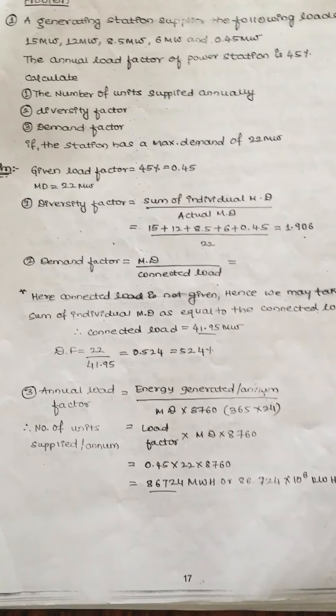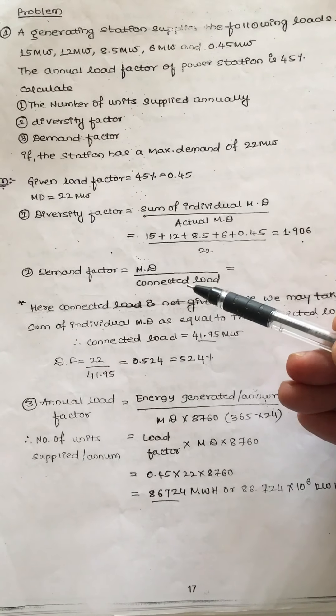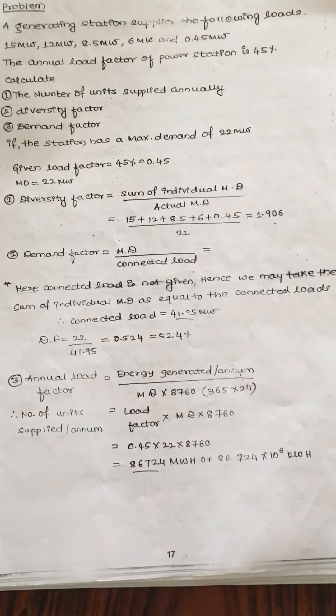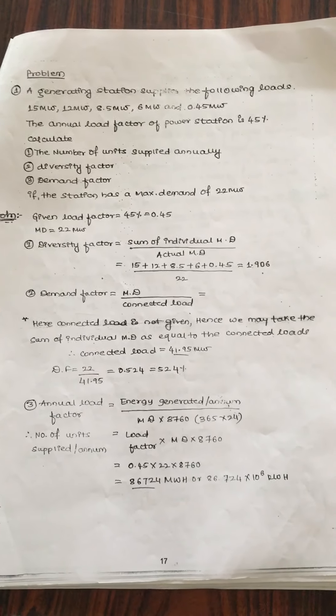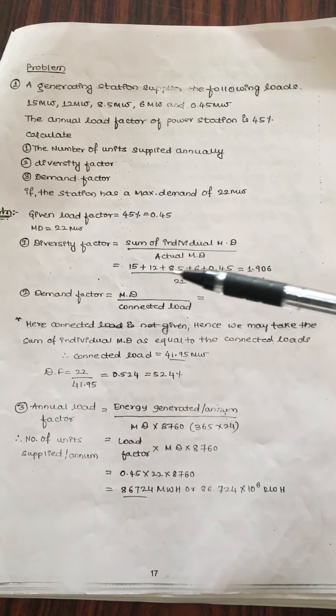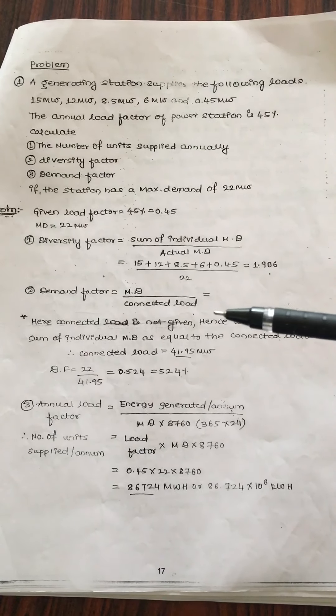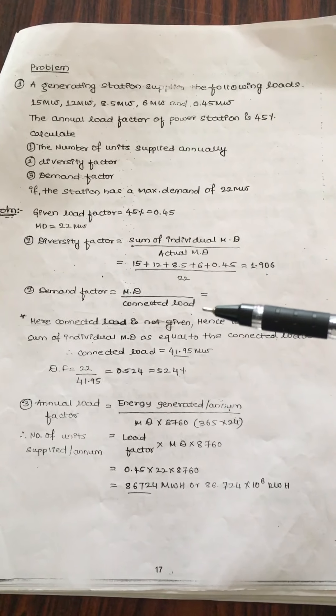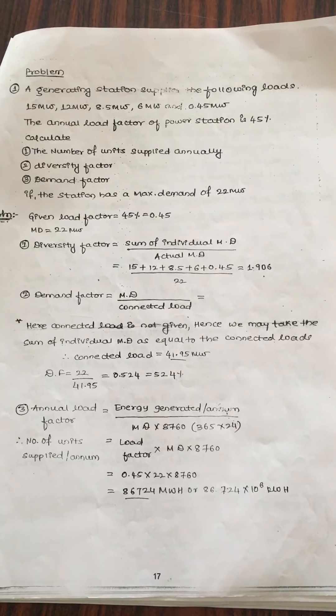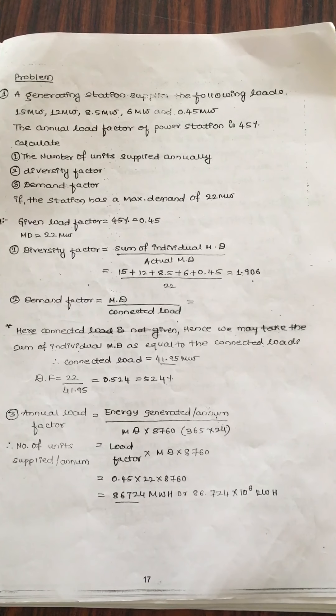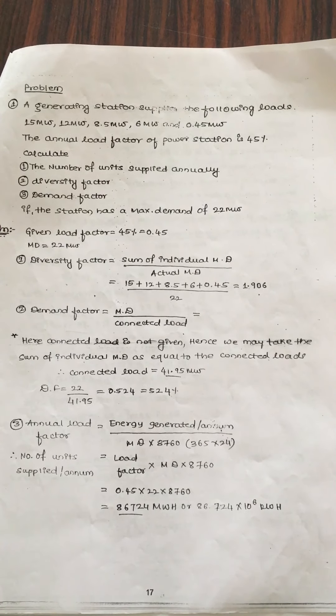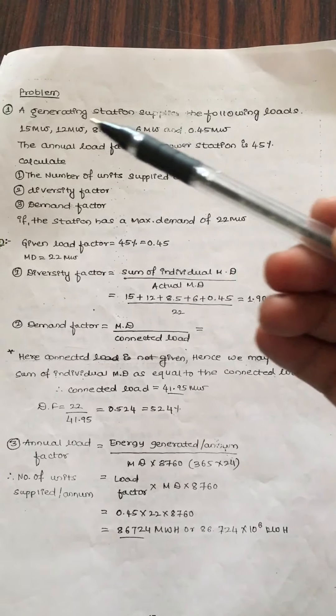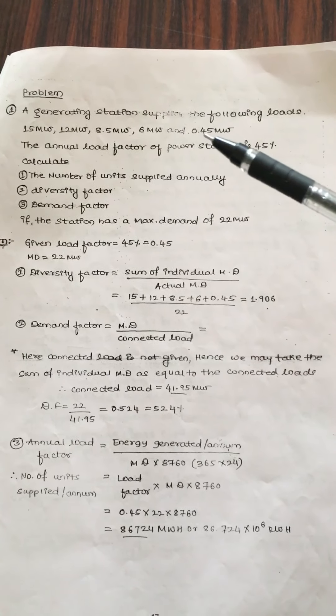Next, to find the demand factor: it is given as maximum demand divided by connected load. We know the maximum demand, but we need to determine the connected load. Since connected load is not given, we take the sum of the individual maximum demands as equal to the connected load.